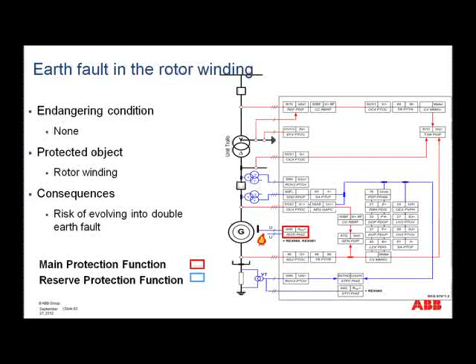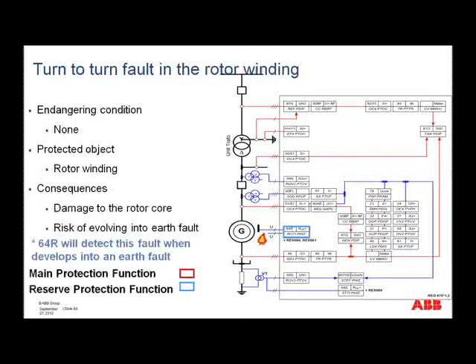So this is just showing the picture where now you have the rotor earth fault, and the main protection function within the IED would be this function for the rotor injection, but of course you would need to have the external hardware as well to make the injection.